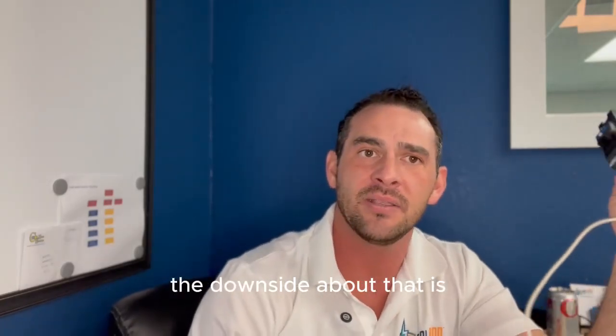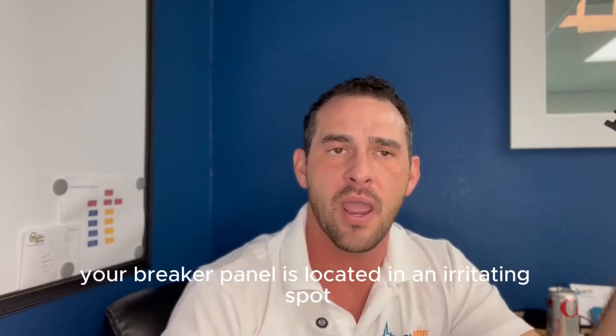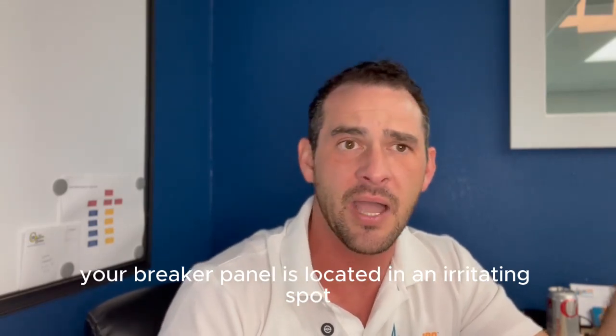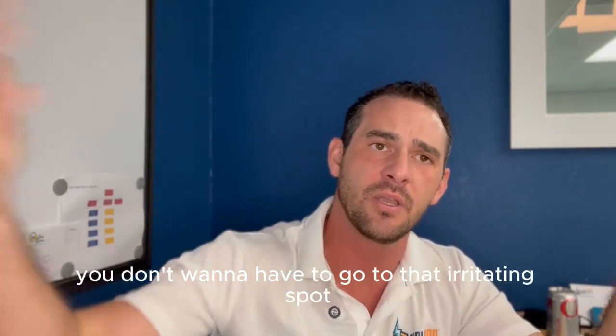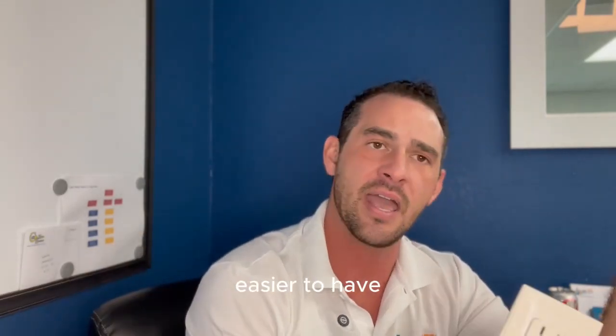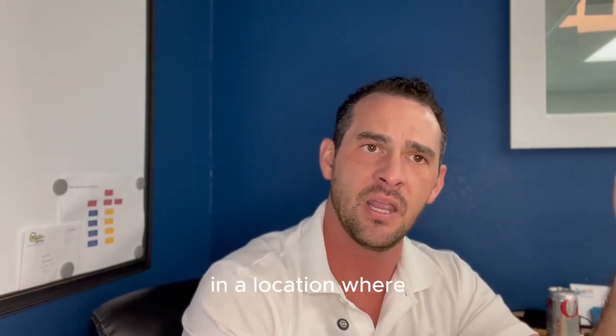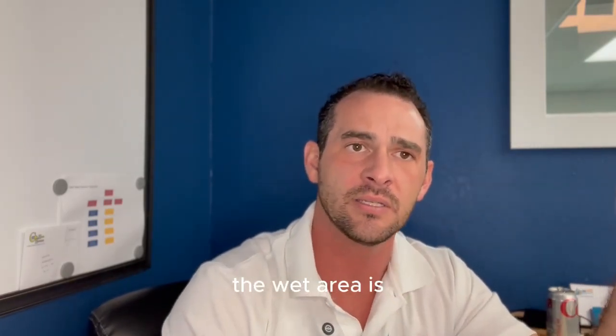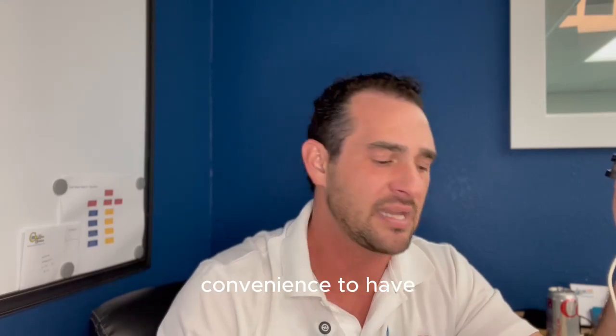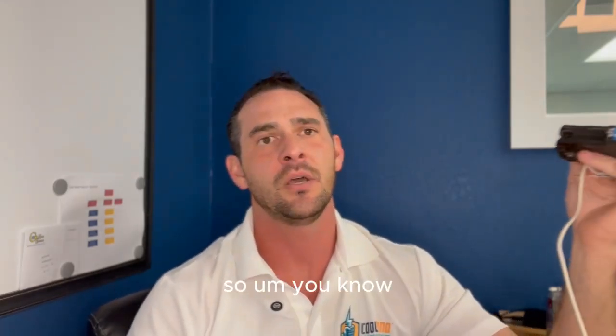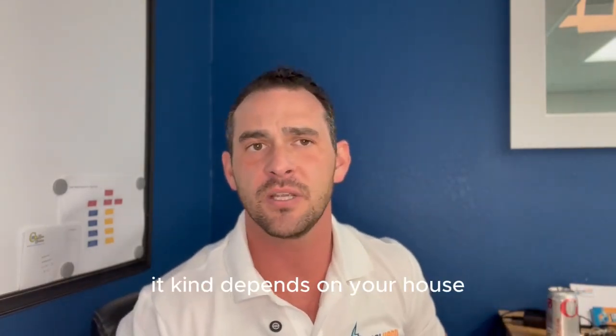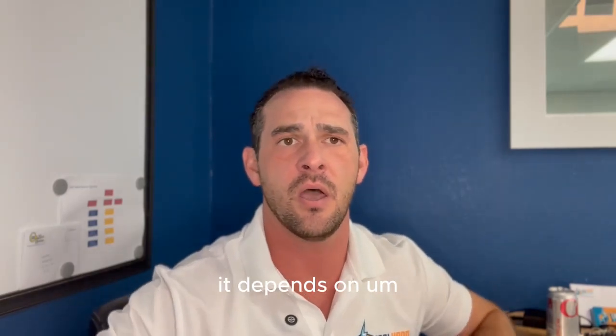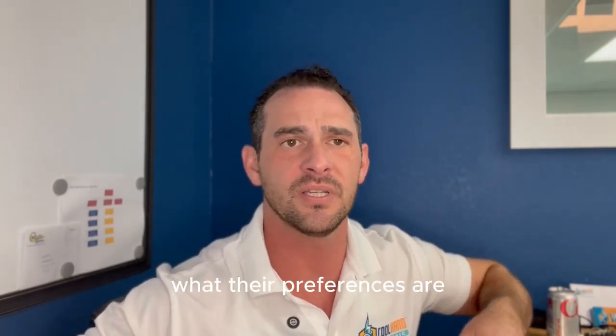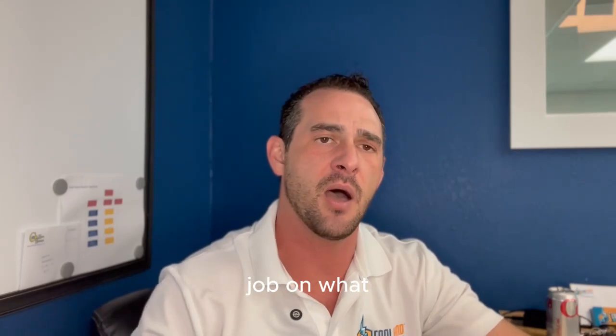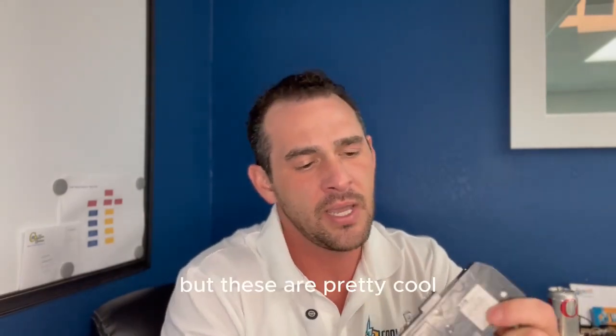The downside about that is, if your breaker panel is located in an irritating spot, if it trips off, you don't want to have to go to that irritating spot. It might be easier to have the reset in a location where the wet area is. So it might be a convenience to have the GFCI outlet. So, it kind of depends on your house. It depends on the builder, what their preferences are, and how they bid the job on what you would have. But these are pretty cool.